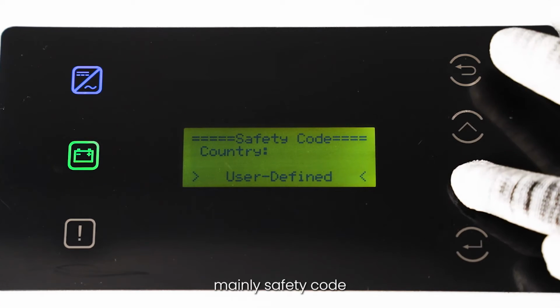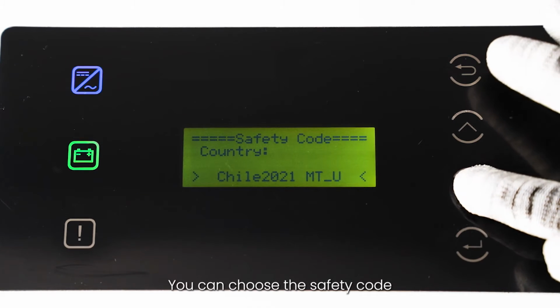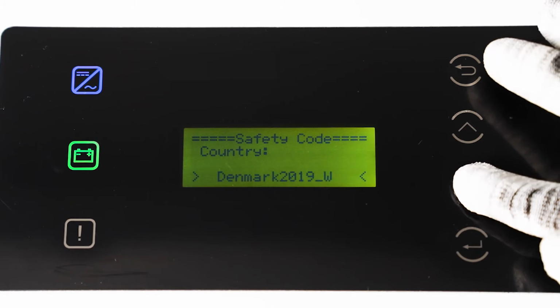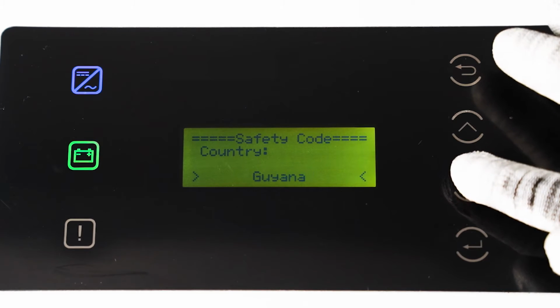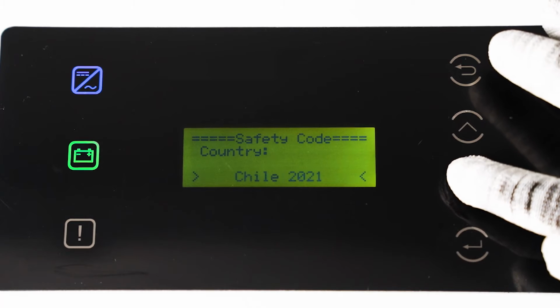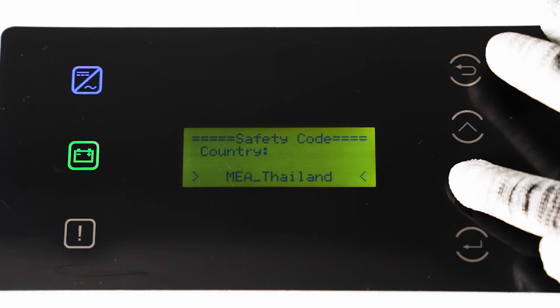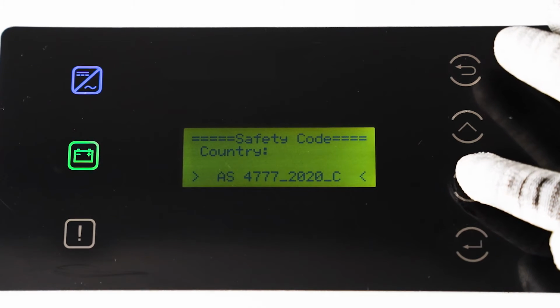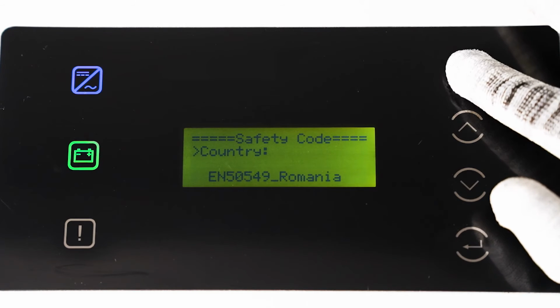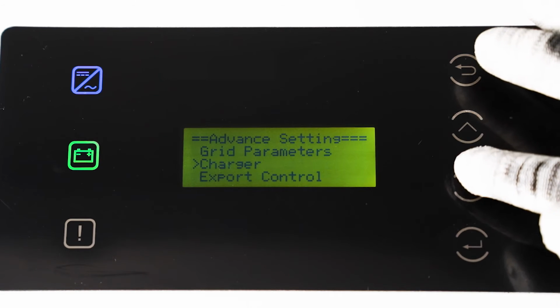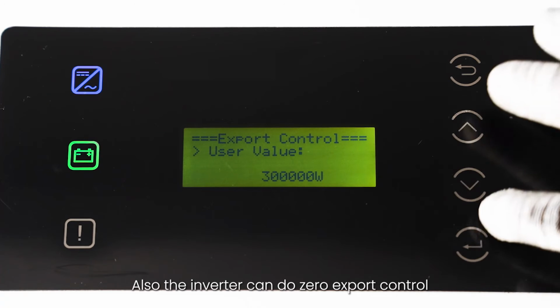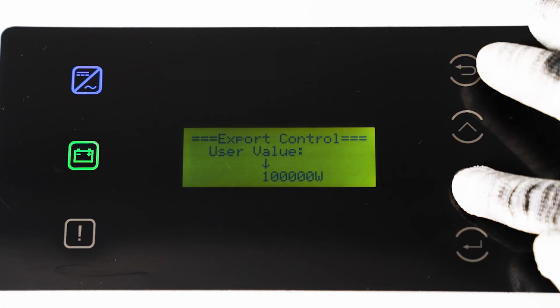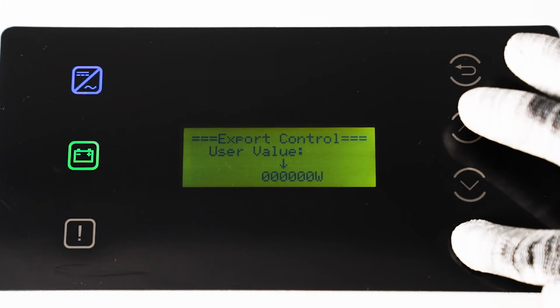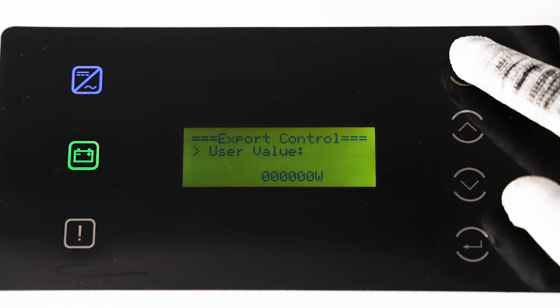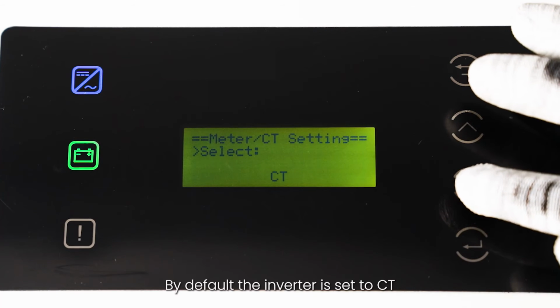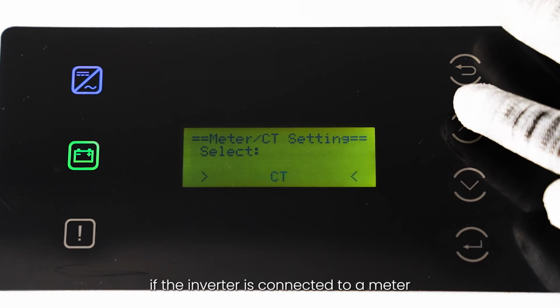For advanced settings, mainly safety code, export control, meter or CT will be involved. You can choose the safety code according to the local requirements. Also, the inverter can do zero export control. By default, the inverter is set to CT, change to meter if the inverter is connected to a meter.